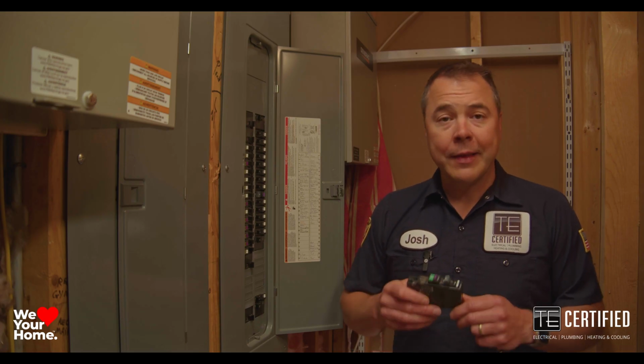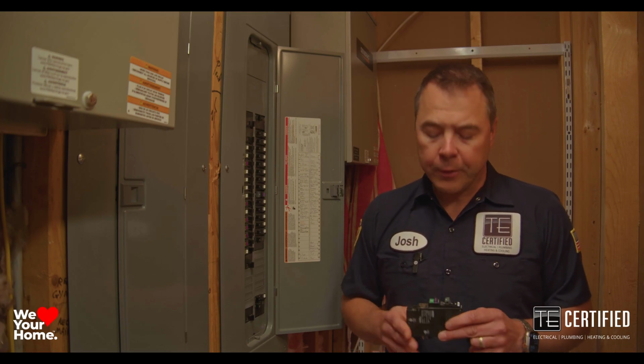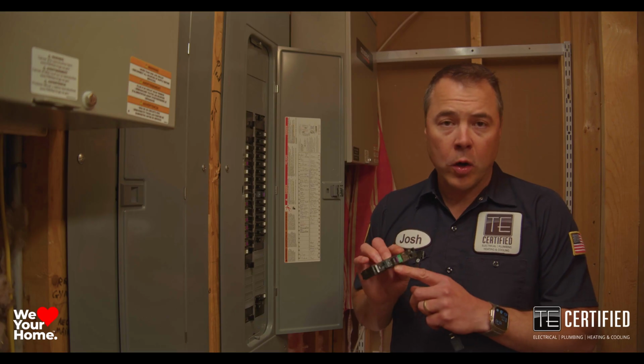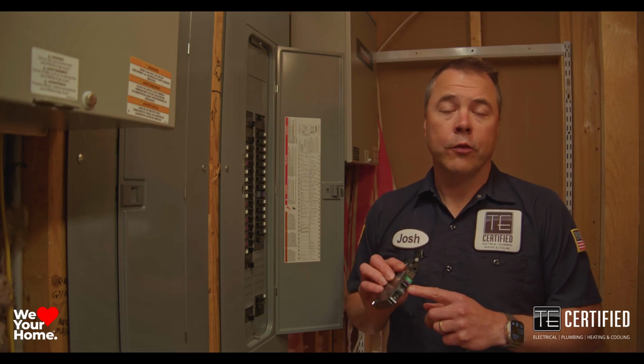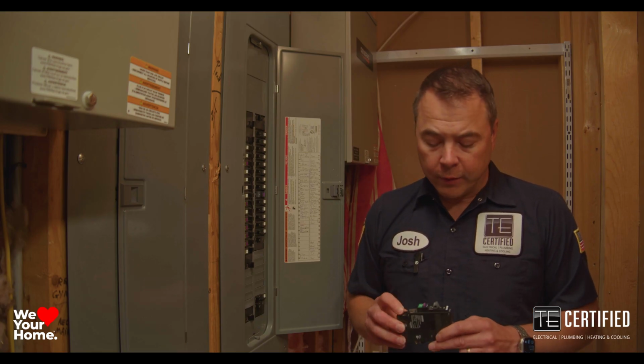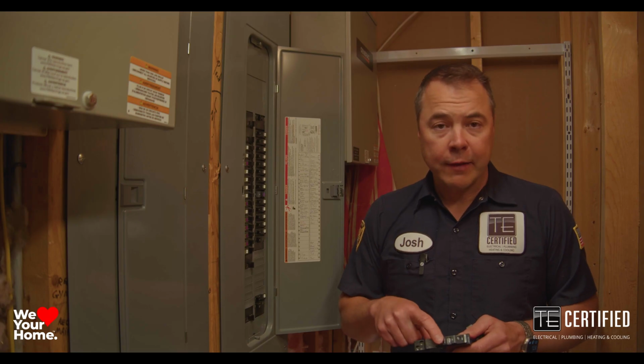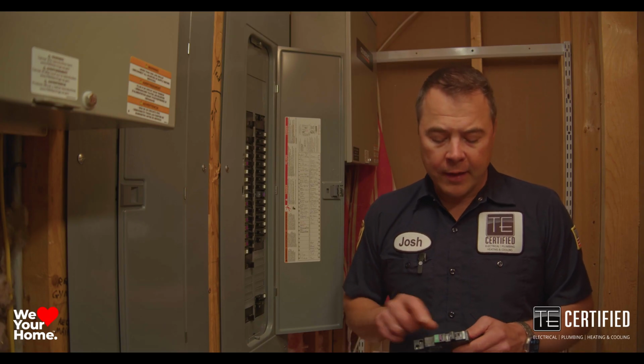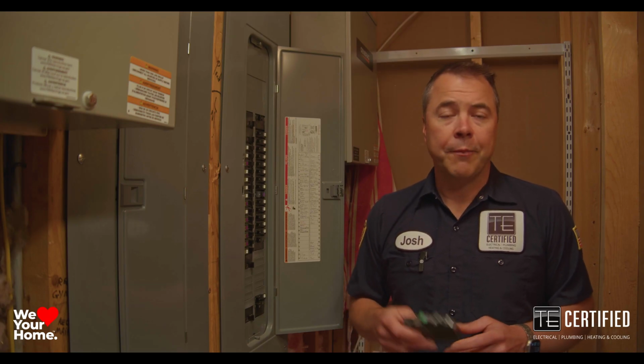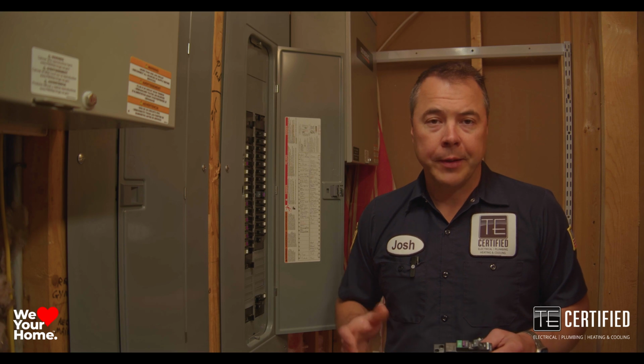This particular brand that TE installs, the QO model, actually has an indicator light on it, and it will tell you why the circuit breaker tripped. These can also be tested monthly by hitting the test button, just like any other GFCI device, and it will trip, and then you can reset it to make sure the breaker is working properly.